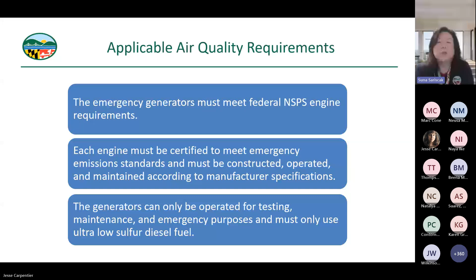And they can only be operated for testing, maintenance, and emergency purposes, and they can only use ultra-low sulfur diesel fuel. Our requirements are not as stringent. They are allowed the 50 hours of non-emergency operation, but not for peak shaving or demand. I think there's a section in the rule that still allows that. But they are allowed up to 50 hours of non-emergency for things that we do not classify as an emergency. But it's still pretty restrictive. And as you can see with the data centers, they're so restricted to meet the 25 tons that they're not even going to be allowed the 50 hours per engine. Next slide.